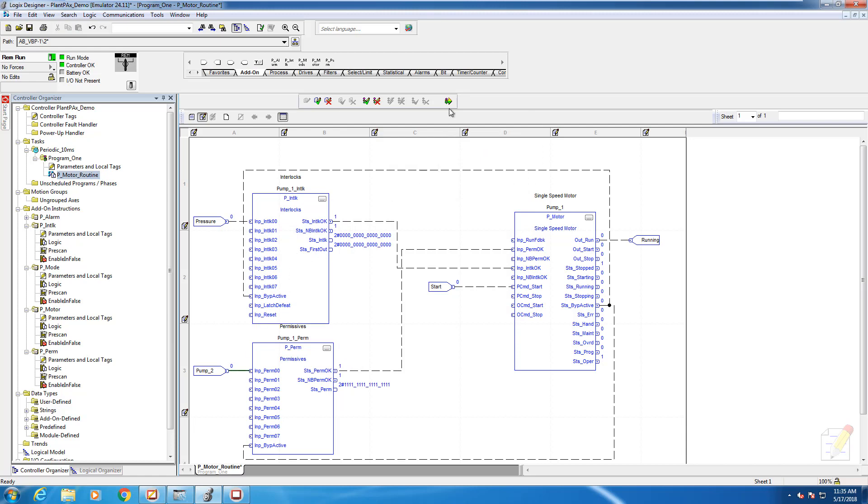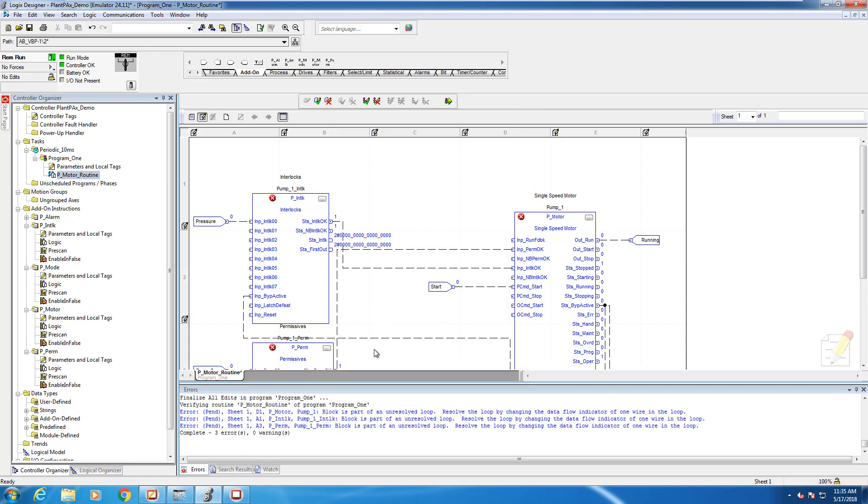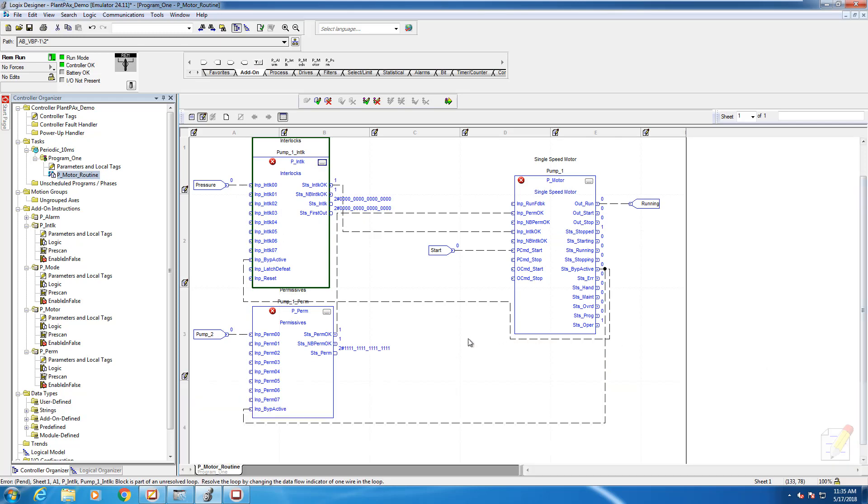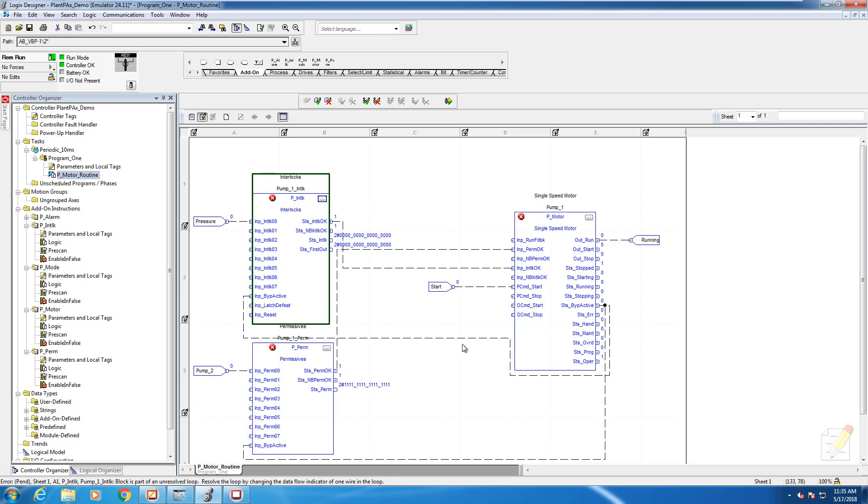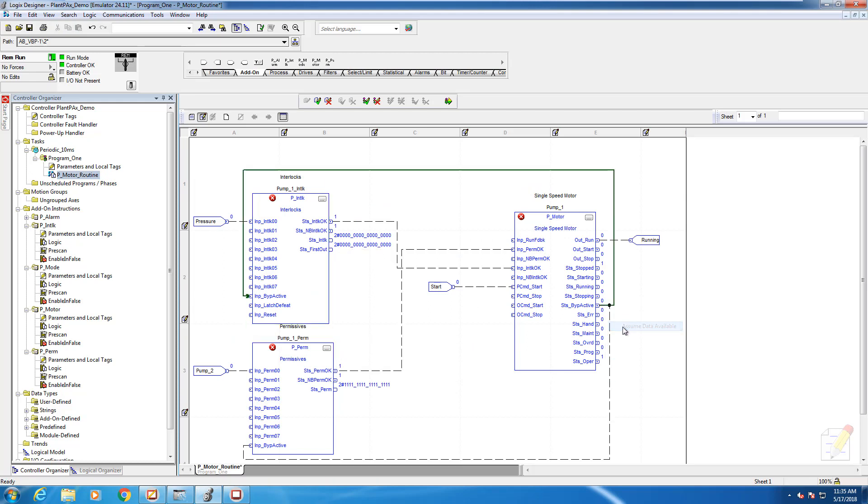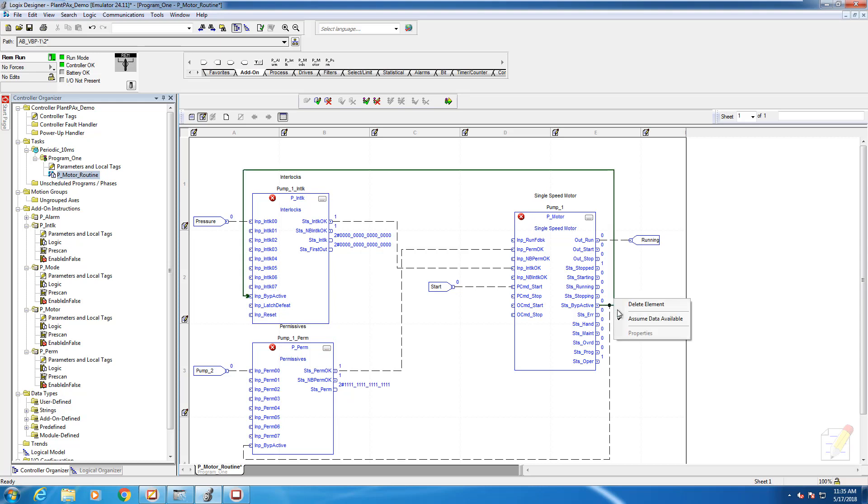I'm going to finalize the edits. Oh no, Jack, what happened? It did not verify, and the reason is because we have a circular reference. We're wiring an output back to an input. So we've got to assume that data is available, and we do that by right-clicking on the wires and checking off assume data available for each of the wires.